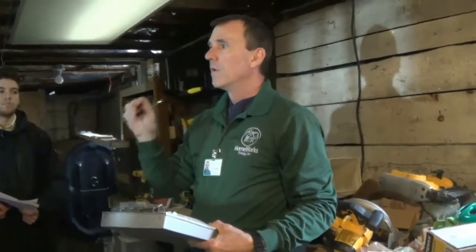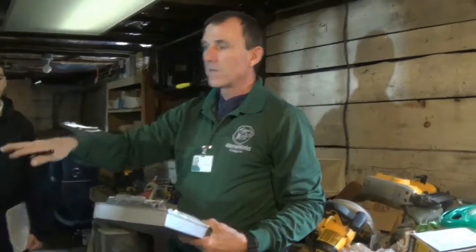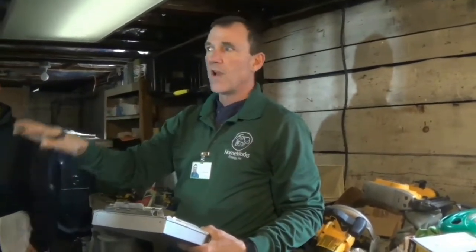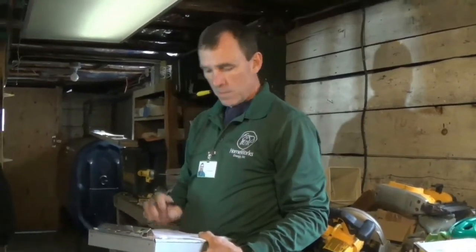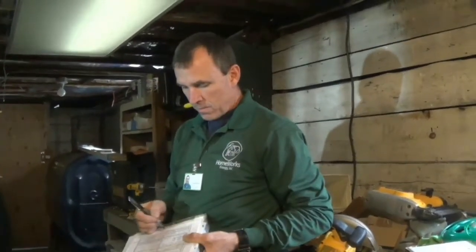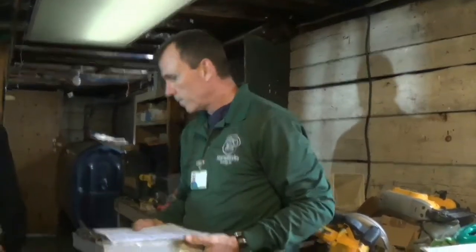And then after everything's cooled off down here, we would start all over again and test for spillage and draft for this one first, turn it off, turn the heating system on, test for spillage and draft on that one, leave it on, come back, turn this back on, test for spillage and draft on the domestic hot water tank to see if, under natural conditions, without the house fighting as much as it was, any of these appliances pass. So we're not ready yet to circle pass-fail down here. So there's a little bit more work to do.